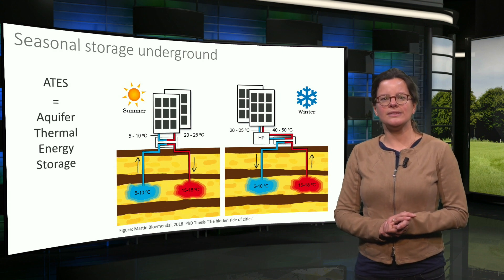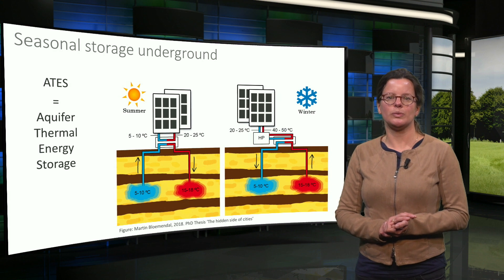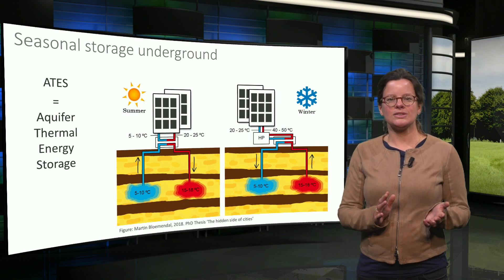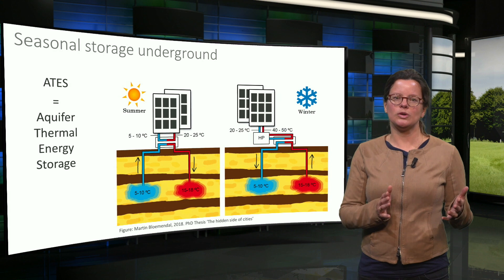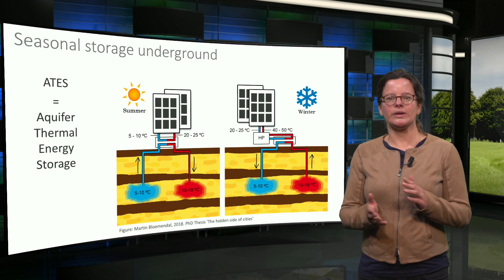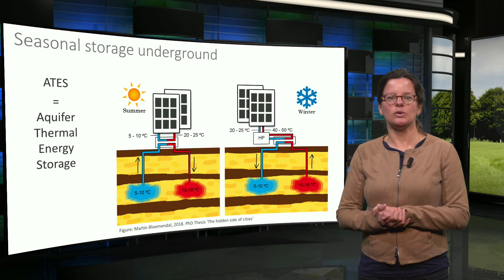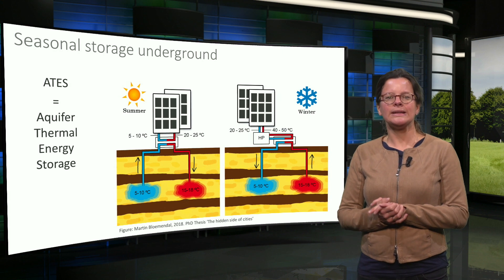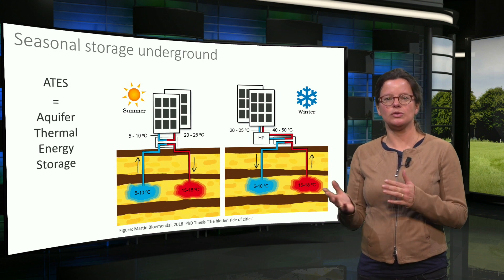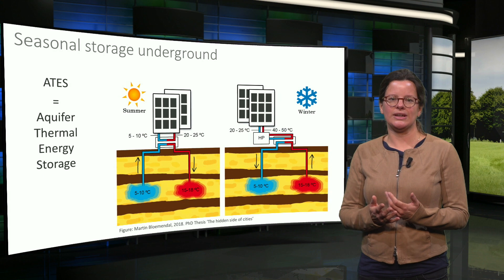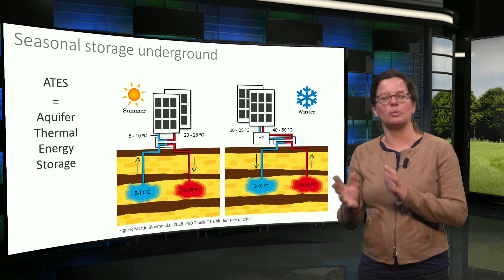In these systems, two wells are drilled, which will become a cold well and a warm well. In summer, groundwater is extracted from the cold well. It passes through a heat exchanger in order to cool a building. The heat from the building is transferred to the groundwater, which is then injected into the warm well.